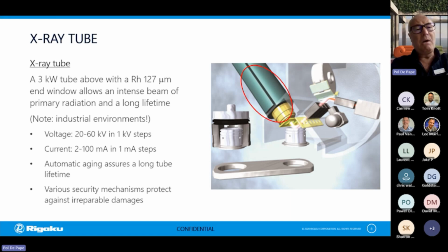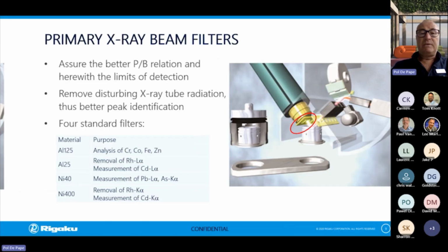But we can still go up to 60 kilovolts, up to 100 milliamps. And we also use tube aging. So in case the equipment was switched off for a longer time, tube aging will make sure that you assure the longest tube life possible. And also various security mechanisms protect against irreparable damages.